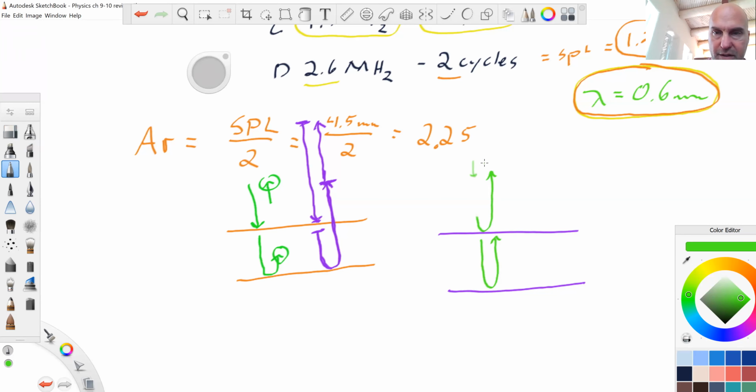An incident beam was coming down this way. It hit here, it is reflected. Some of that sound went through, hit this one, it's reflected, and it catches up. You can see that this is going to catch up with this tail. As we go further along, here's that first echo, and there's that second echo. They're basically attached. They've become one long echo.